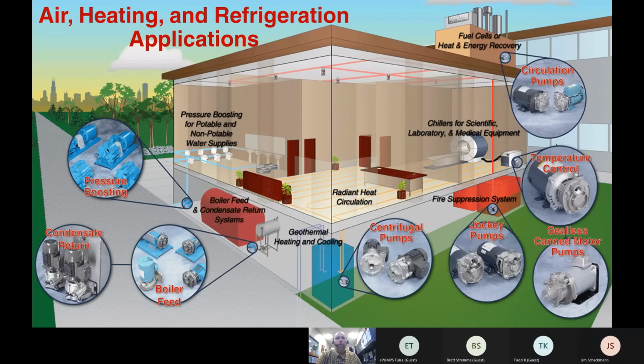And of course, we do the condensate return, we do the boiler feed. Boiler feed, if you're not familiar, is where you're refilling a boiler that is under pressure. So you need another high pressure pump to be able to overcome the boiler pressure to be able to refill the boiler while it's still running.